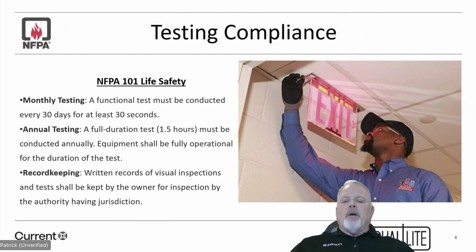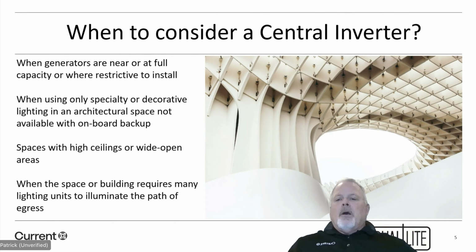The other thing that you'll find with a lighting inverter versus the other types of product is that a lighting inverter will also maintain testing records. I believe our units maintain up to 30 records. So if you did have an inspector come in and they wanted to know when the life safety products were last tested, you can actually pull this directly from the unit itself if you can't find the log that you're supposed to maintain. When to consider a central inverter?